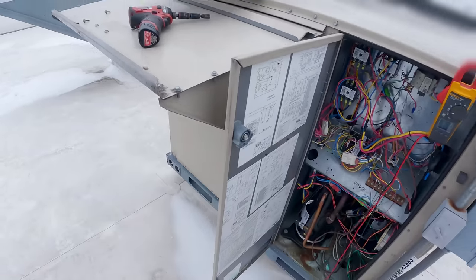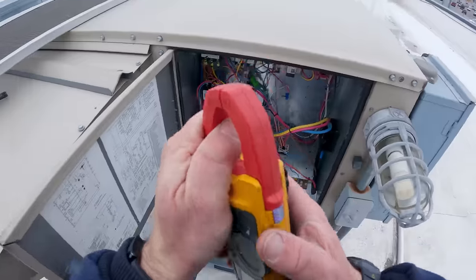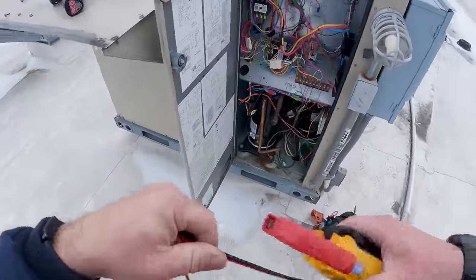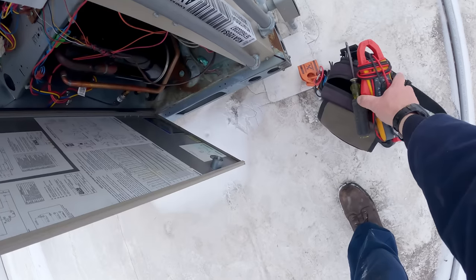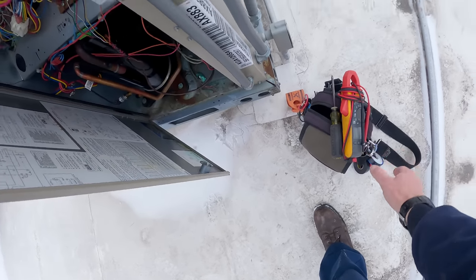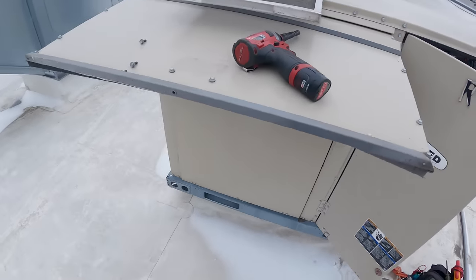If they did that you'd be able to just tell it exactly when you want things to lock out instead of having to add snap-disc-style thermostats and things like that. Let's go downstairs and see how things are as far as the building being negative. We are bringing in a little air — didn't get too crazy. We'll put all that back together in a minute.